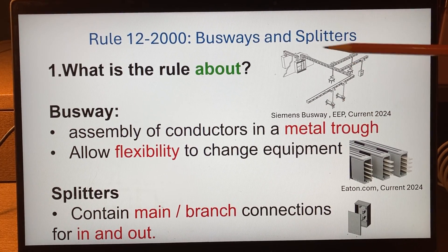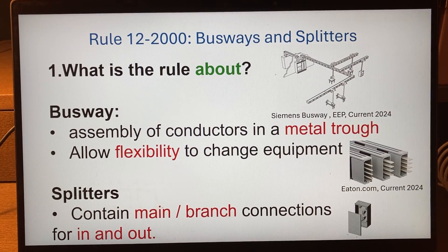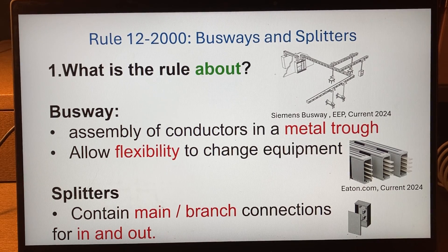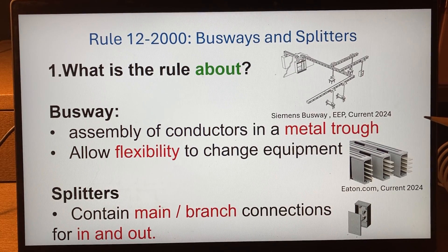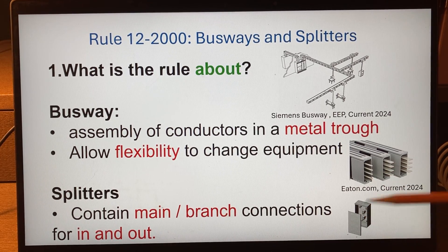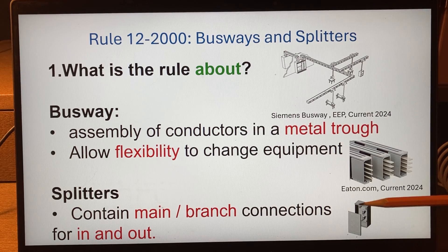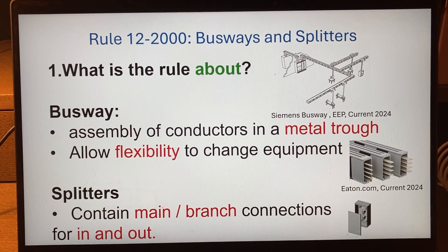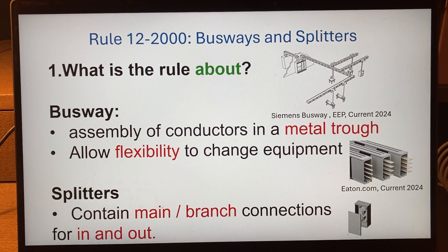We use busways so that they allow us flexibility to change equipment in our power distribution system. They are either ventilated or unventilated — the unventilated ones are called totally completely enclosed. Splitters are similar to busways, but the bus bars or terminal blocks are provided with main and branch circuit connections for in and out. If a splitter exceeds 4,900 millimeters, it is actually considered a busway, so they follow the same rules.